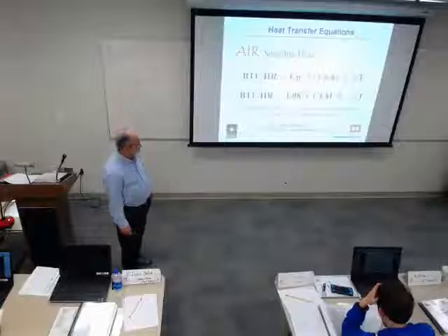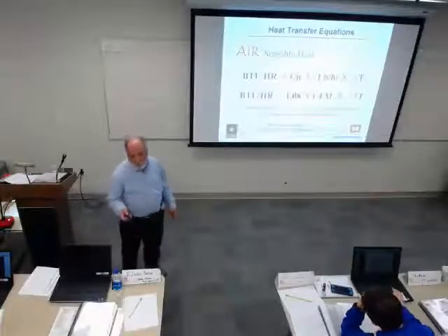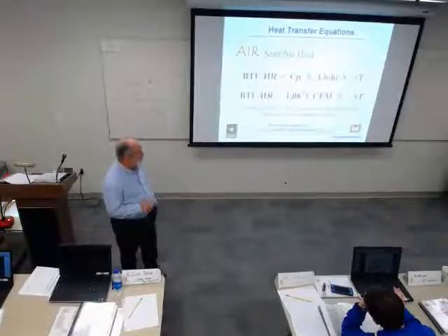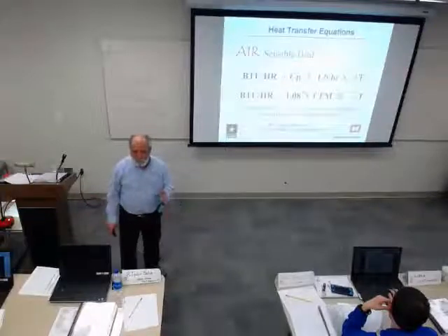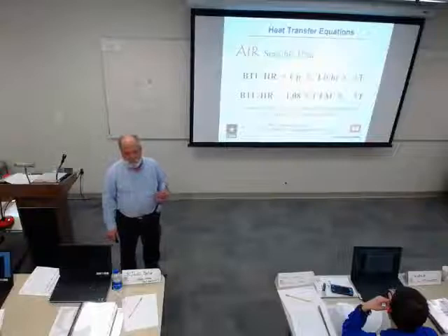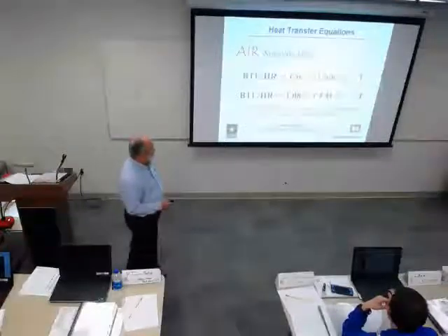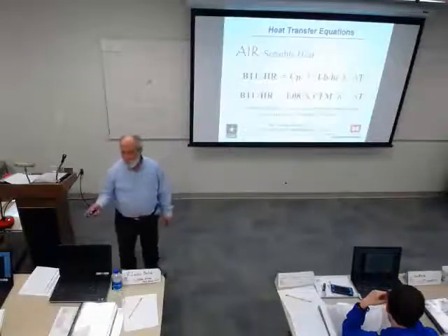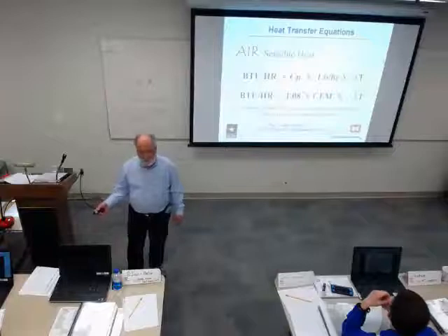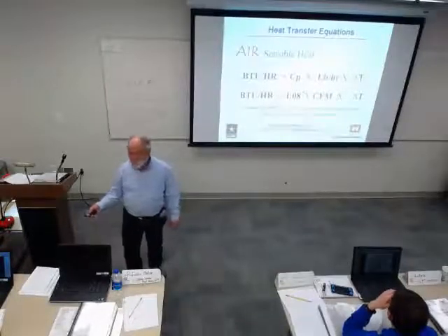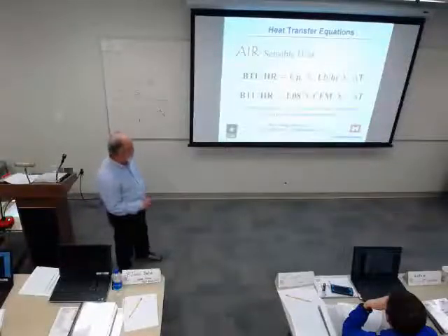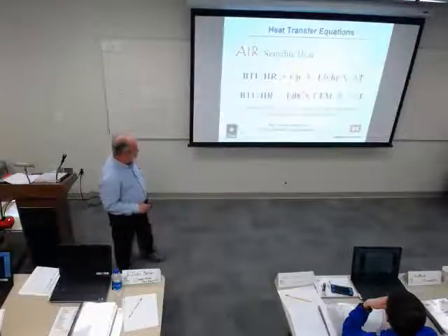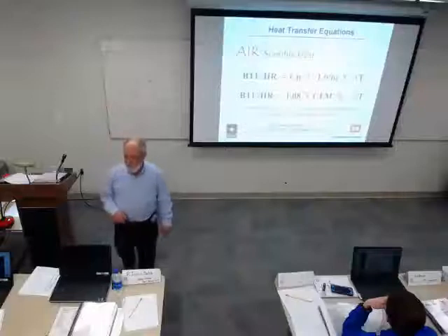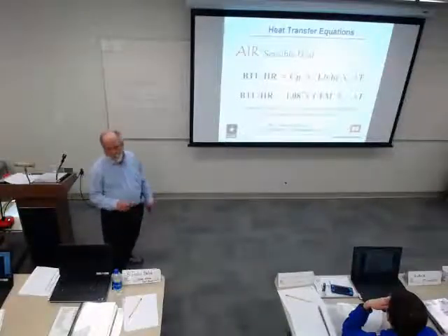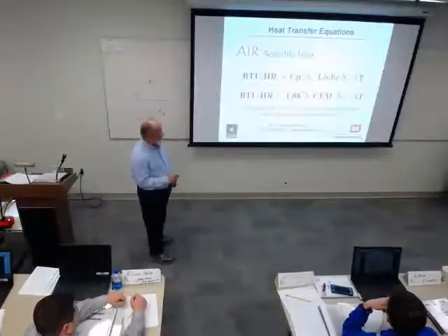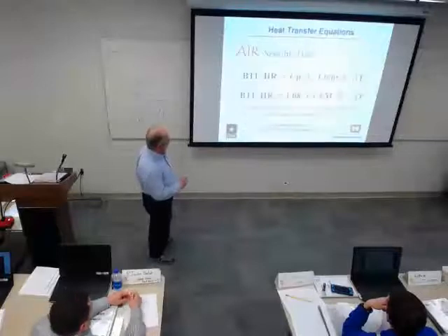And so for that condition, if I wanted to know the energy input from the coil, I would use that 1.1. On the other hand, if I'm measuring the hot side, the air coming out, and that's where I measure the airflow rate, and I'm using a pitot tube without going through all the corrections, then I'll probably use the 1.08. So whichever is the cooler side, if you're measuring the air where it's below 40, then you'd use the 1.1. If the temperature is above 40, and I forgot what the other limit is, then 1.08 is what you use. Anyway, we'll do an example with that, and you'll see how that works. Okay.